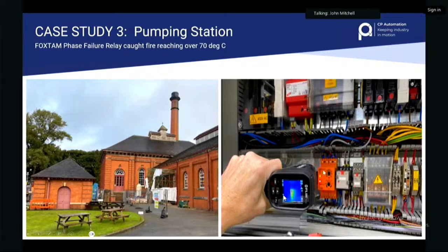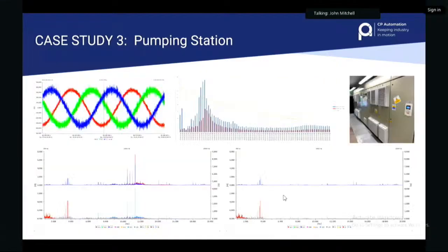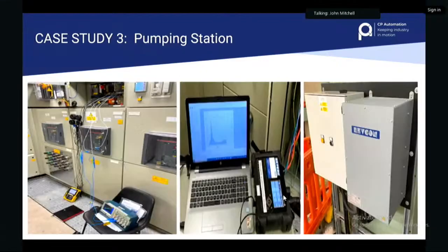This is another site where they have a phase failure relay—I don't know if you're familiar with a product called Foxtam—and here's a DIN rail surge arrestor. This unit caught fire due to superharmonics; it was arcing inside a little resistor inside the device. We installed a Sine Tamer and an HHF and cleared up all the signals. The customer was over the moon.